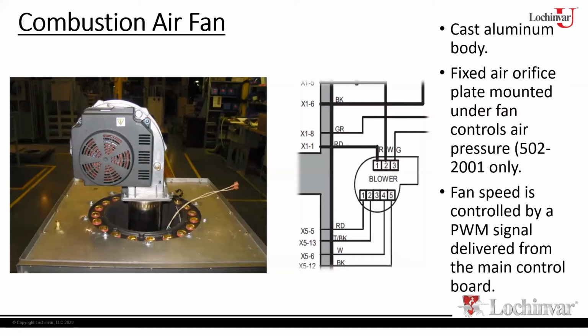We do have a fan tester available that you can use to try to narrow that down. Basically, it will send a false signal to the blower, and it's looking for feedback from it. If it gets that signal that says the fan's responding correctly, then the fan's probably not your issue. It's more than likely the module at that point. So again, it's one of those items more often than not.